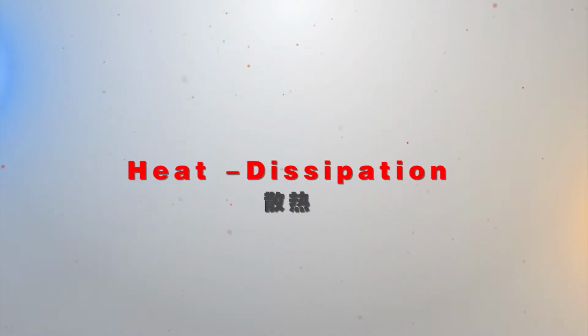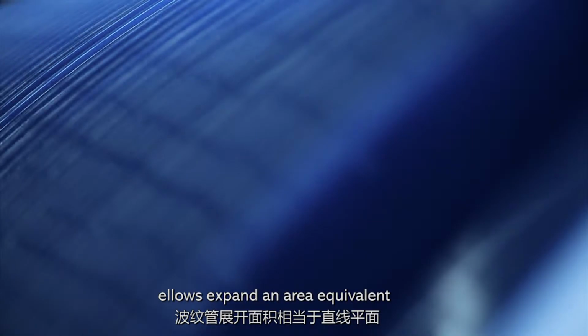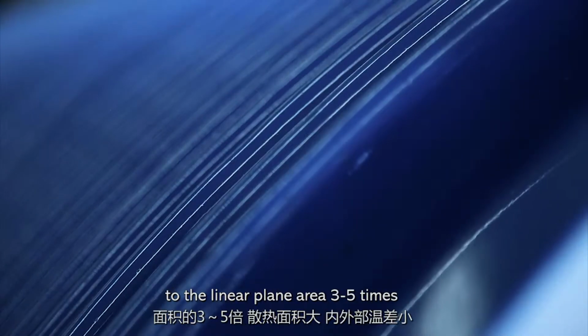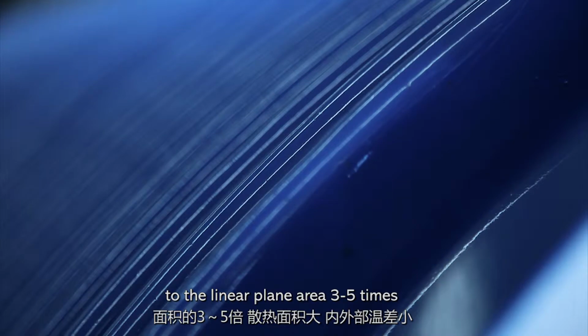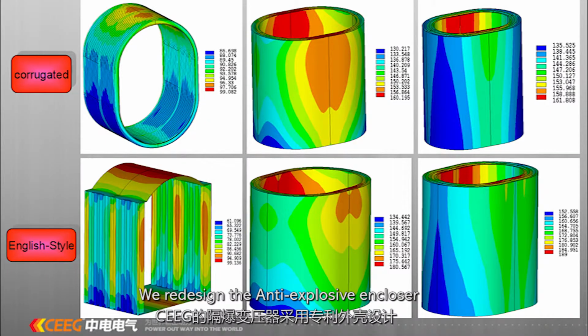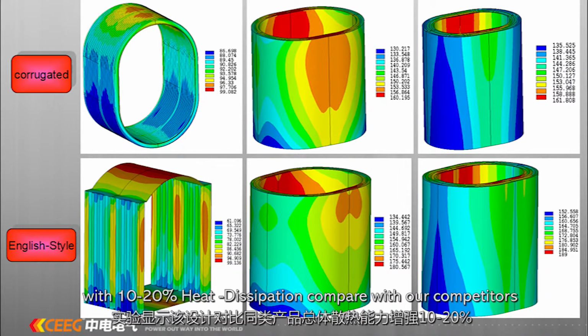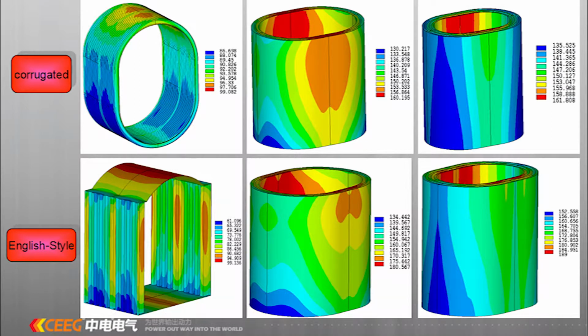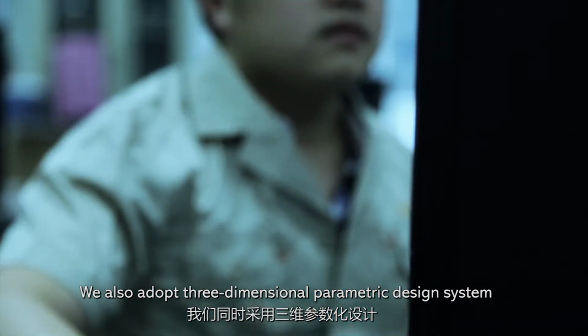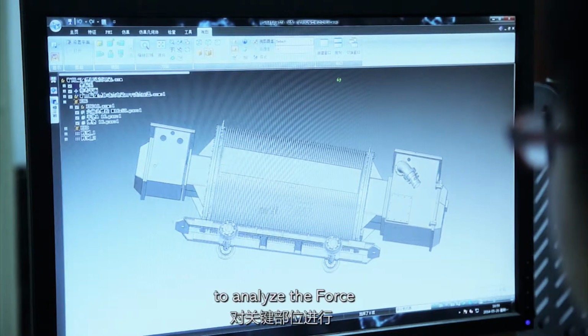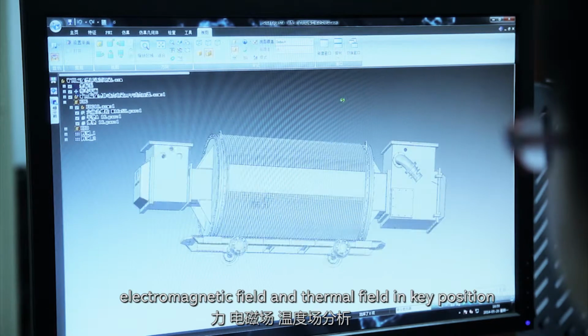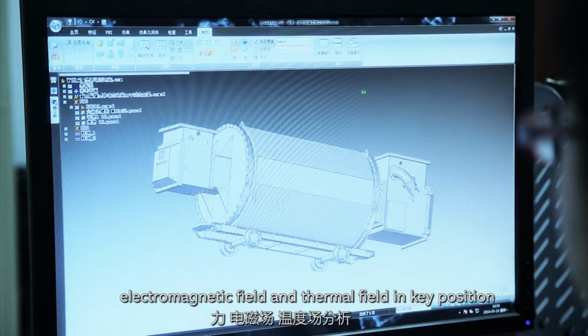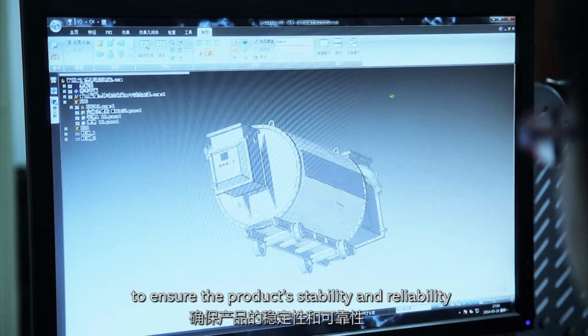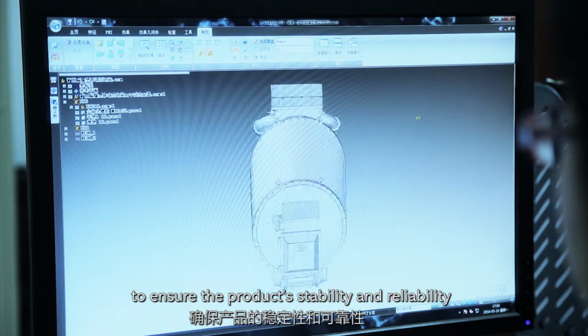Heat dissipation. The bellows expand the area to 3 to 5 times the linear plane area. We redesigned the anti-explosive enclosure for 10 to 20% better heat dissipation compared with our competitors. We also adopt a three-dimensional parametric design system to analyze the force, electromagnetic field, and thermal field in key positions to ensure the product's stability and reliability.